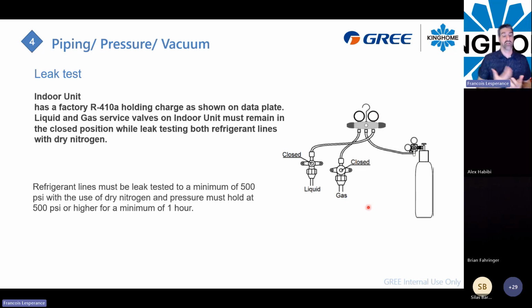You will apply 500 psi. Make sure it's holding for an hour. Okay. Just make sure you don't have micro leaks. Also, you can use your soap to spread it on the flare. When you're using soap, just lay it there for 15 minutes minimum.